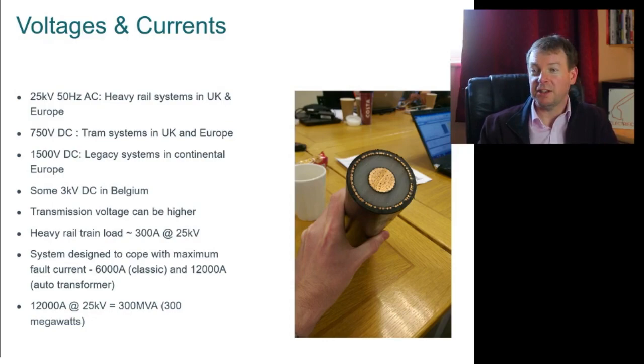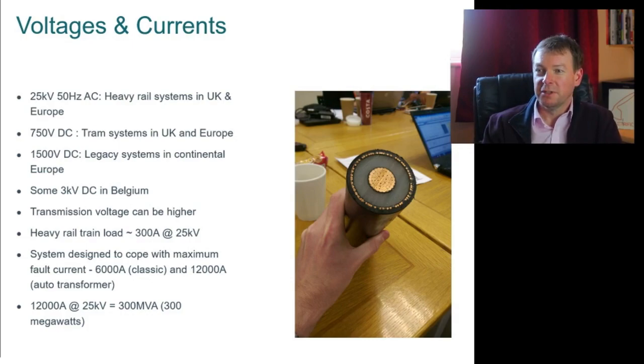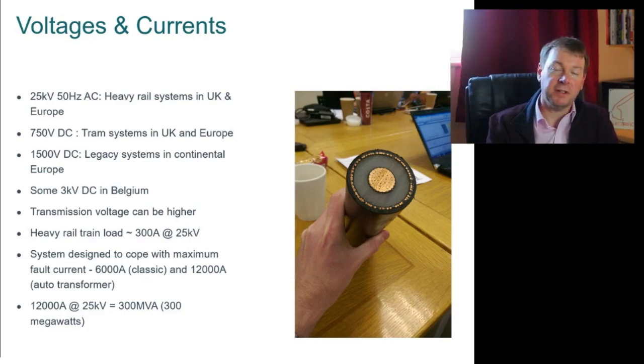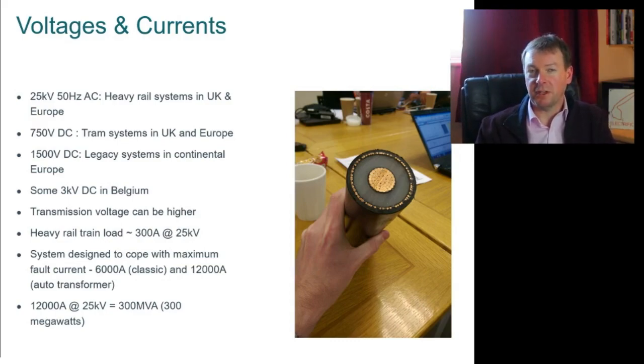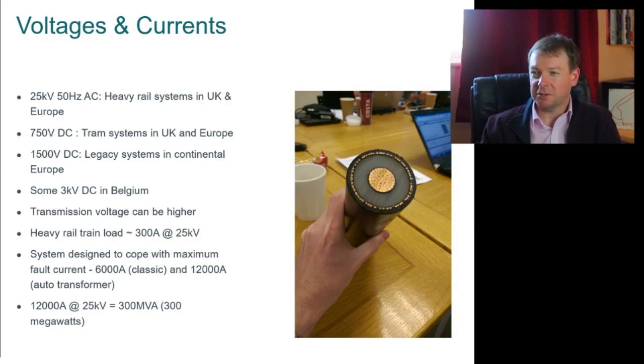kV AC. Now that's the voltage that the train sees, but it is possible to transmit power at a higher voltage than the voltage that the train sees. So for instance, on high-speed lines we often use 50 kV to transmit power, but then the train still only sees 25 kV, and we use a clever feeding arrangement called auto transformer feeding to achieve that.